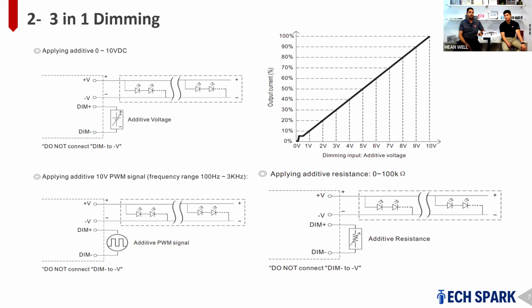The first method is by applying an external 0 to 10 volt signal. If you apply 0 volts, you'll dim off the light, and if you apply 10 volts, you'll get full brightness. By changing this voltage, you get different percentages of output current, which is reflected in the brightness.